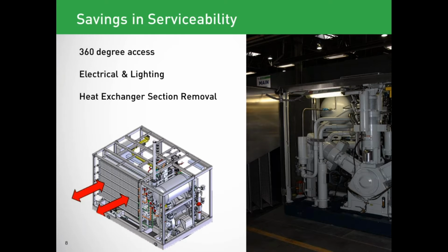The next thing is improved electrical location and lighting of the package. So there are two lights strategically located inside of the compressor package that illuminate all of the major service areas, allowing the technician to see what he's doing without needing a flashlight or a trouble light inside of the package. Eliminates the need for non-classified lighting to be brought in, which could lead to issues with the presence of gas. The electrical location, there's an electrical panel inside of the compressor package accessible from the service access way, which allows the technician to do any troubleshooting, I/O checks, etc. from within the compressor package, where he's protected from the weather.